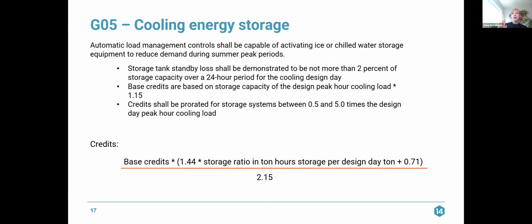The storage tank standby loss shall be demonstrated. Oh, and so this is the requirements for the tanks themselves and how they're going to operate. The storage tank standby loss shall be demonstrated to be not more than 2% of storage capacity over a 24-hour period for the cooling design day. So this tank is insulated. It's probably buried. You know, we are not losing any of that cooling to the outdoor air. Maybe it's located inside. But you have to show a calculation either from the manufacturer or from the design team that shows that you are not losing more than 2% of your storage capacity over one day for the cooling design day.